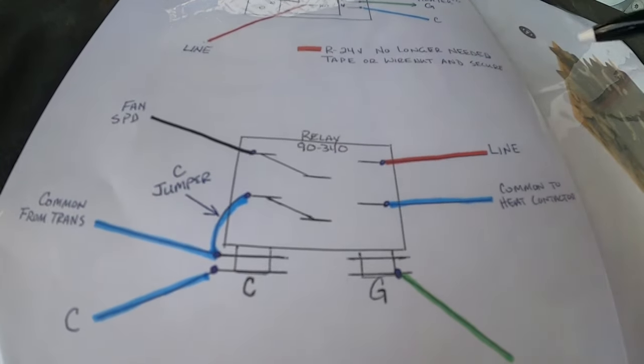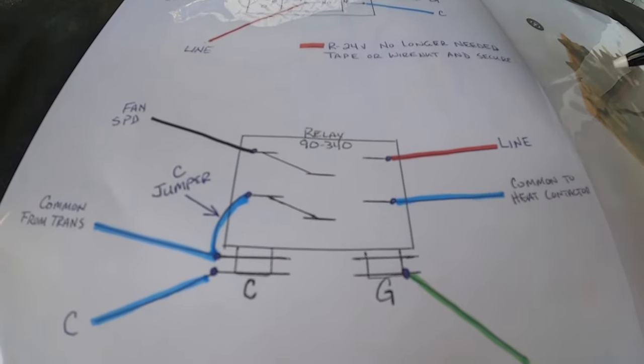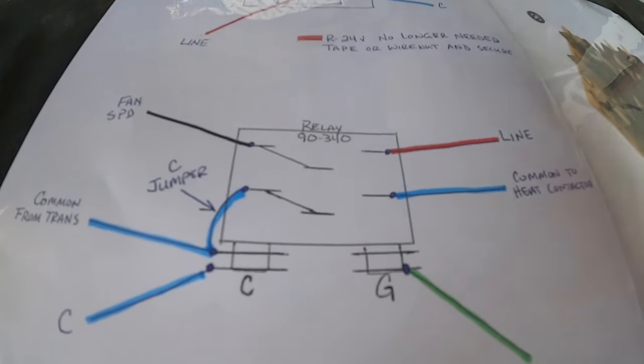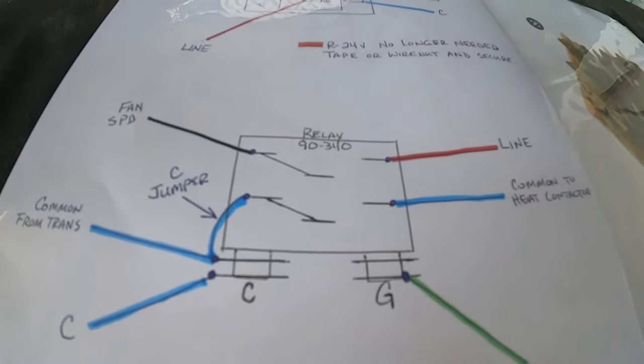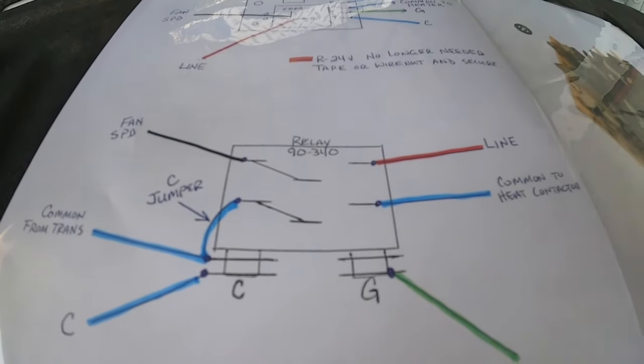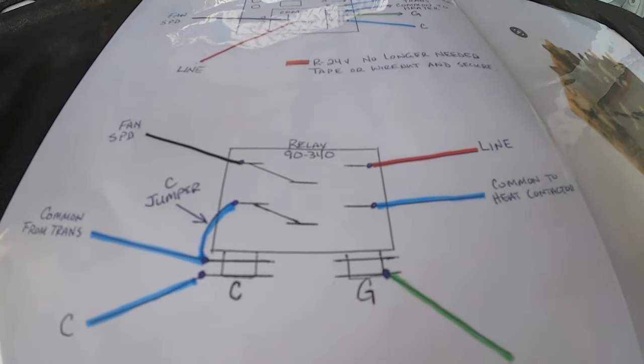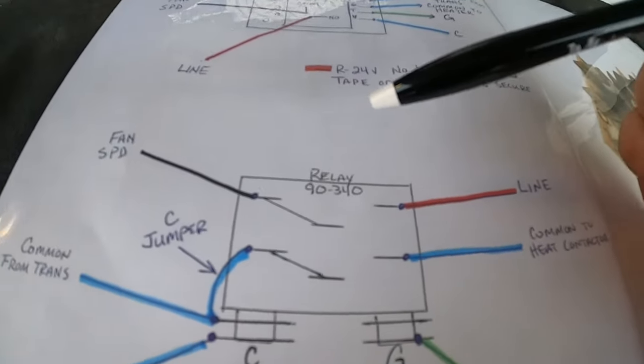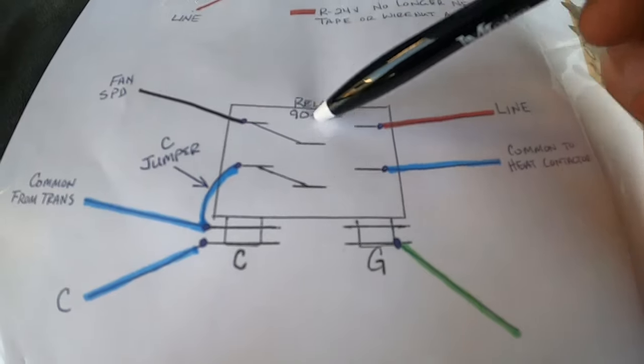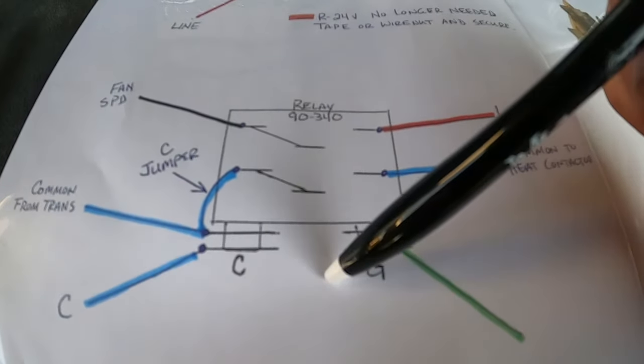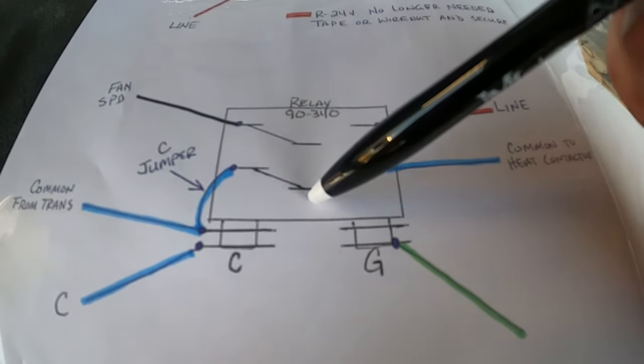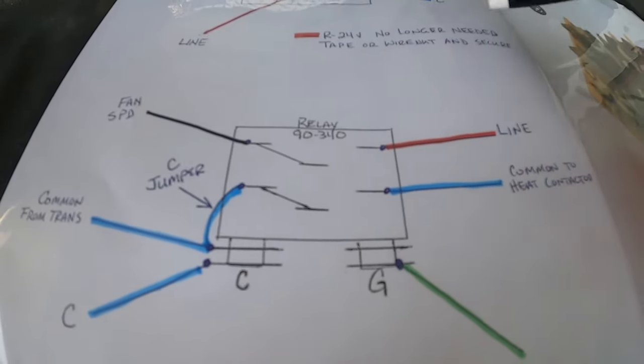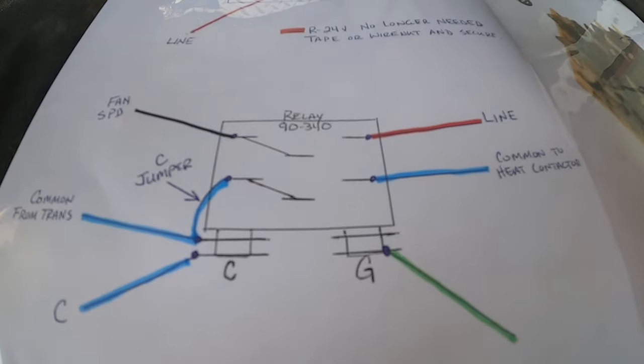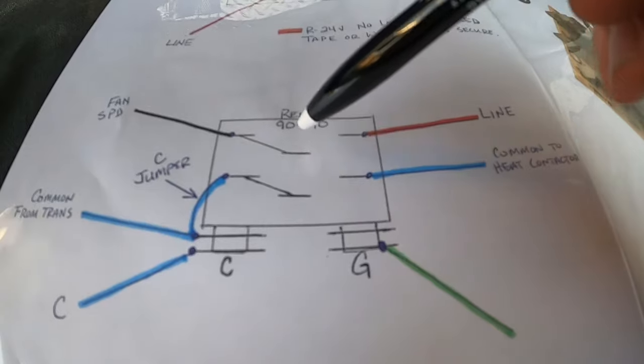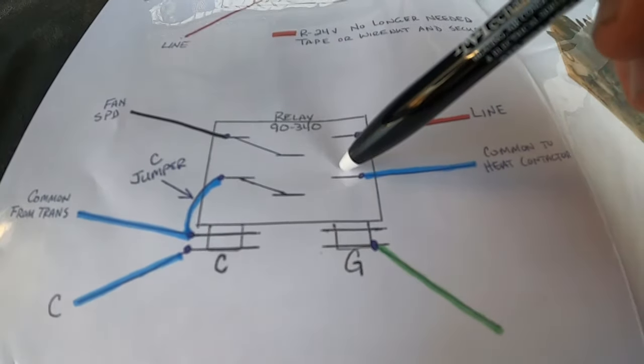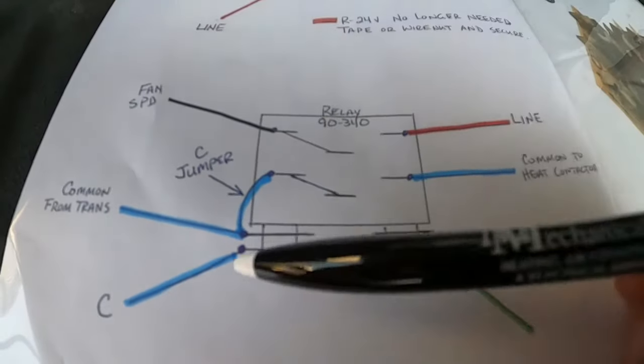Trane, every system has a way set up that they want to make sure that you have airflow when your heat strips are on. I'll cover the other scenario in a minute, but with the older Trane air handlers, you can send 24 volts on your auxiliary heat to your contactor in those air handlers for the heat strips, but it's not going to close unless it gets a common. So what Trane does, American Standard too, they power the motor across this switch when this relay is energized. This one they close and they prove common over to that contactor for the heat strips. So those heat strips in those Trane air handlers will not run unless this relay is closed to confirm we have airflow, and then it proves common to the blower. So that's typically how you're going to wire this one. You're going to run common here.